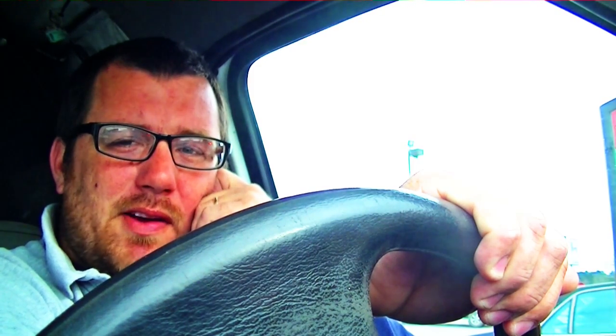Good morning guys, we're here on a service call Sunday morning, right at Thanksgiving, having no heat at a house I went to a few months ago — a Home Advisor customer. We're going to take a look and see what's going on. There's no display on the thermostat; it's a heat pump, so there's no low voltage power. The fuse is blowing or something along those lines. We're gonna check it out.